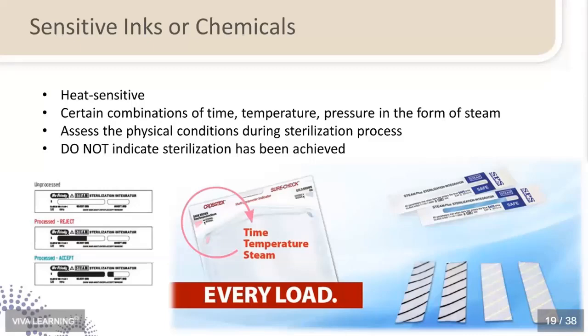When we talk about those chemical indicators, and again, there's a full webinar coming up on that in April, remember that these are simply sensitive inks or chemicals that are going to react to, depending upon what classification of indicator it is, one or more of the sterilization parameters. However, chemical indicators, whether they are built in, like you see here, or they're going to be a type 5, an integrating indicator, like you see here, or it's something as simple as a type 1 sterilization tape that's just simply an exposure process indicator.